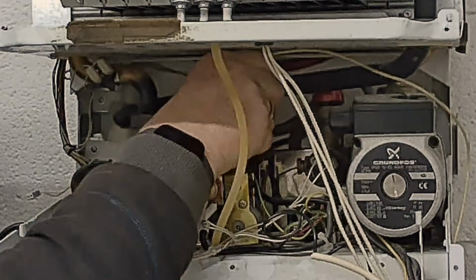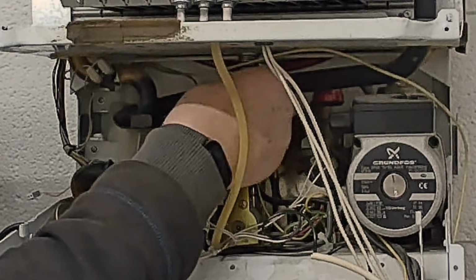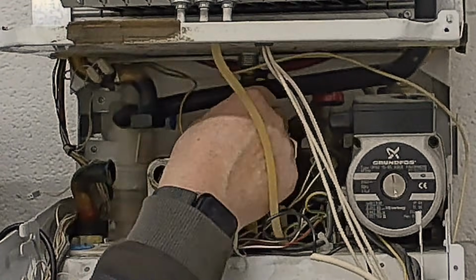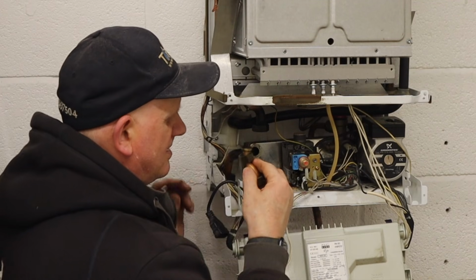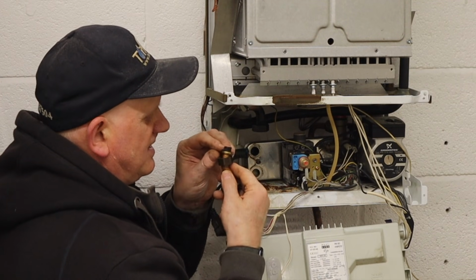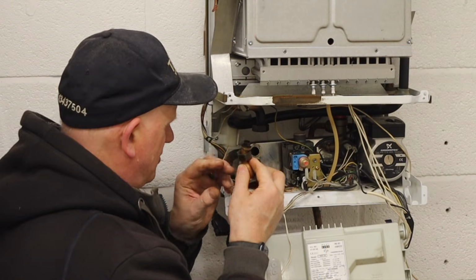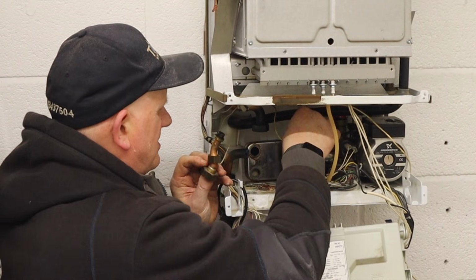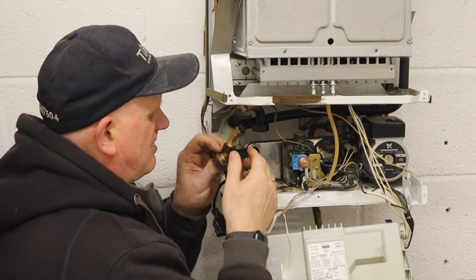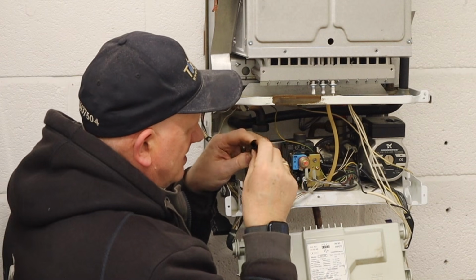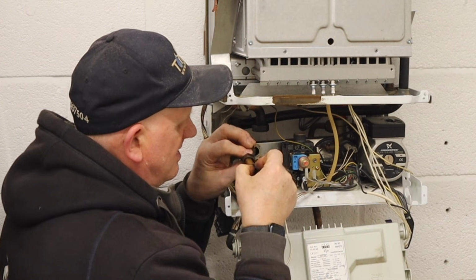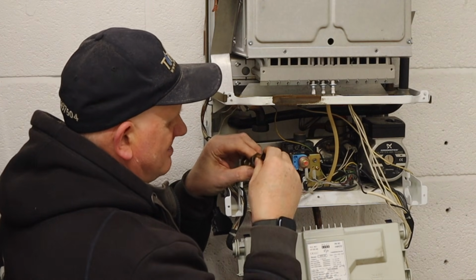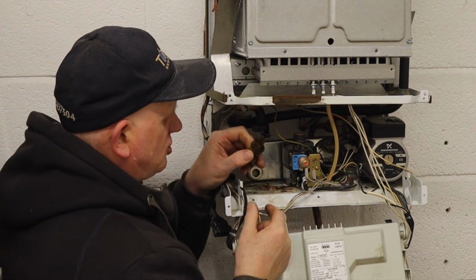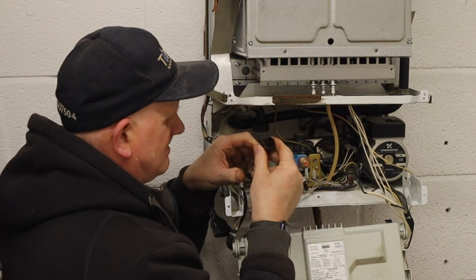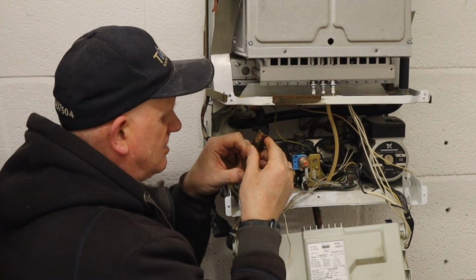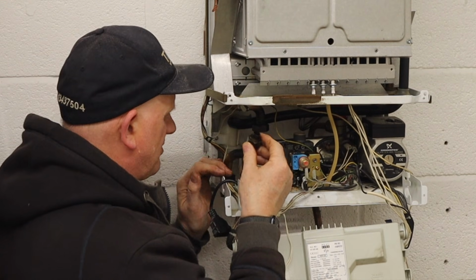It should just twist out now. Then it drops down, and there's a little rubber piece in here which is quite perished. So there's a fibre washer on top of the gas valve, and there should be a rubber washer inside, which as you can see has got quite squashed. So we're going to have to replace that washer - I'll take it off the other one and see if that one's better.